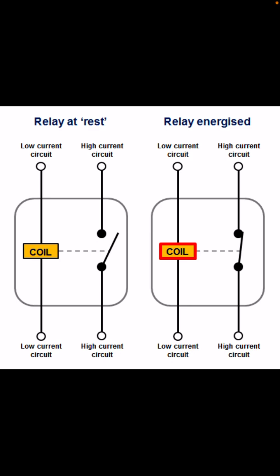So if you look on the left-hand side, that would be a relay where it's not getting its control voltage. So the path's open, it's not letting your input go to its output. If you look on the right side, that would be where you are getting your control voltage. You're getting 24 volts on the coil. So you're getting your input at the bottom of the picture. And then since the contacts are closed, it's going across those contacts and it's going to feed whatever it's supposed to be feeding.